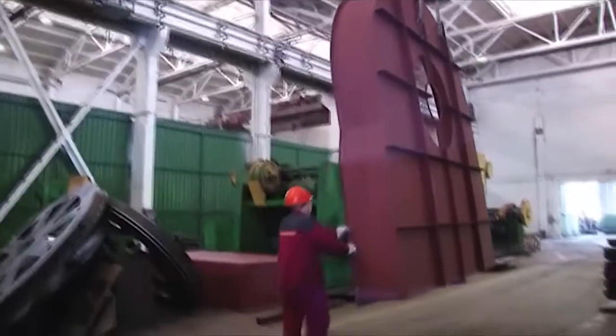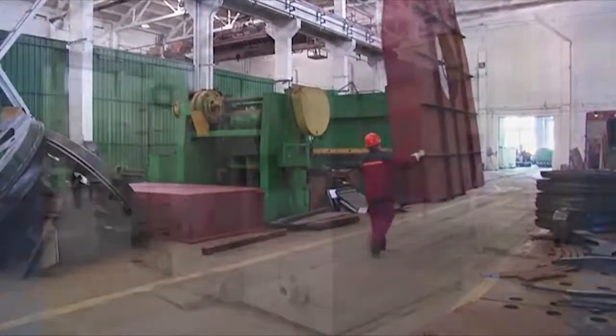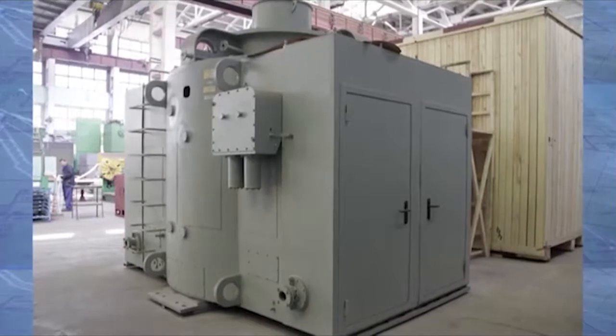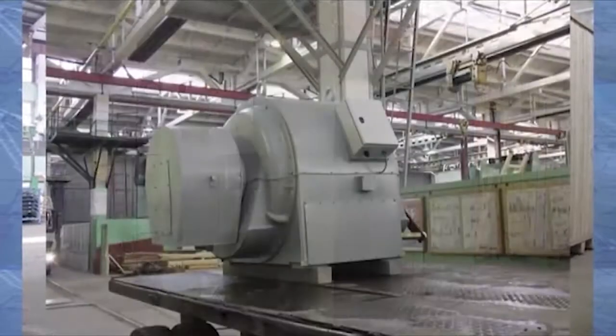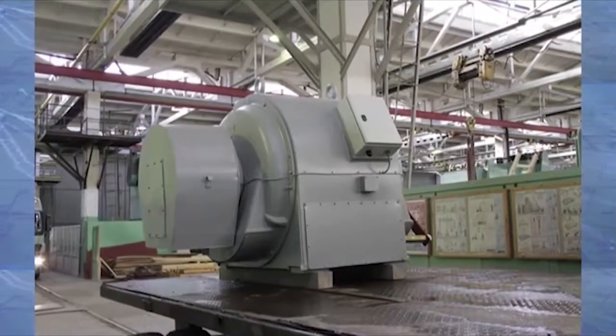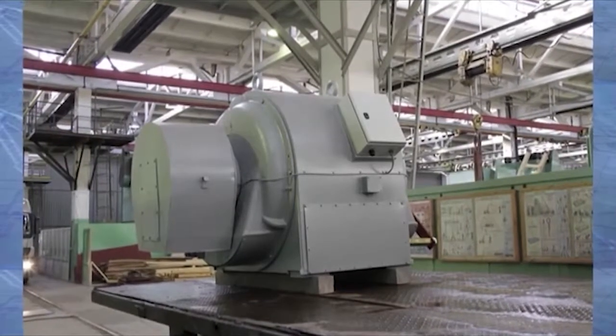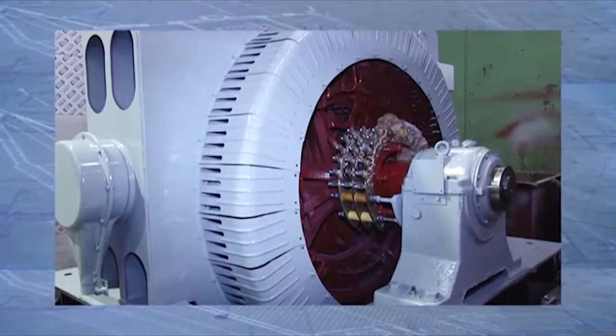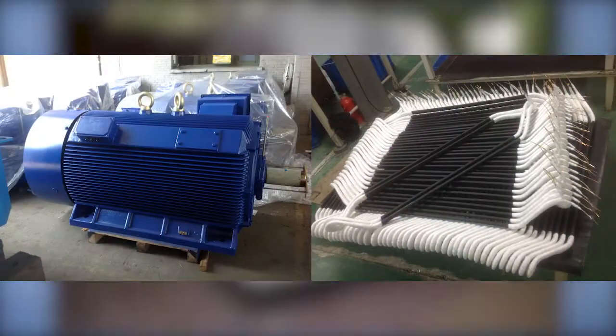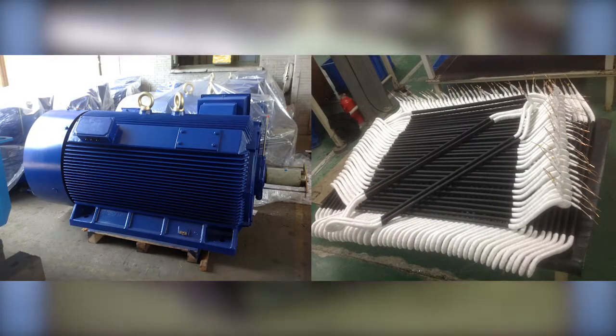Nowadays, the St. Petersburg plant has a complete production cycle, including the development, manufacture and delivery of electric motors of more than 500 dimension types, with overall dimensions of up to 10 meters in diameter and weight up to 165 tons. These are squirrel cage and slip ring wound rotor induction electric motors which are used in industry for the manufacture of pumps, fans, crushers and other devices with high rotational speed.